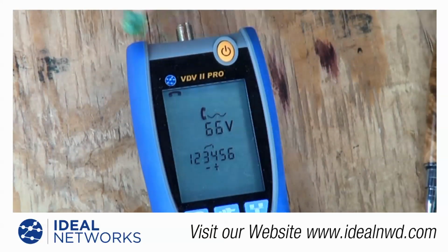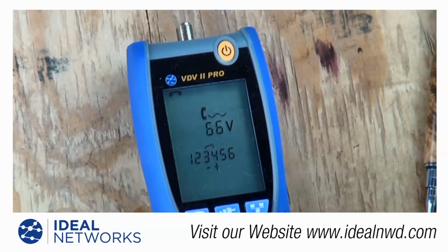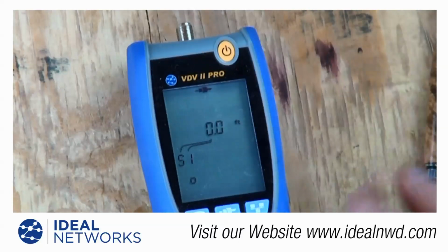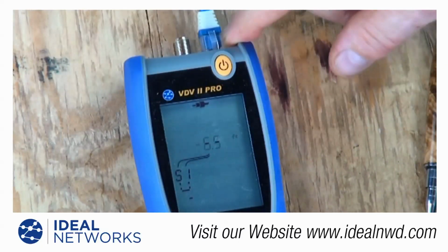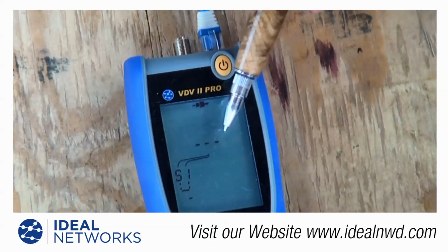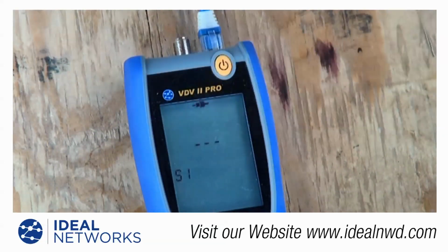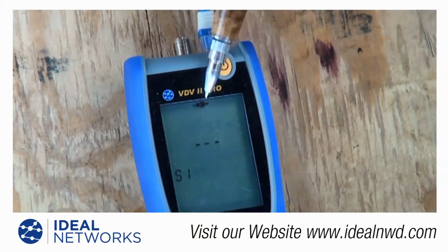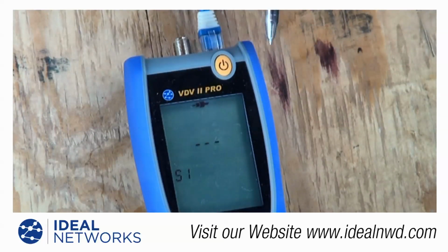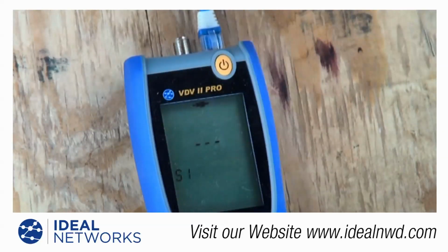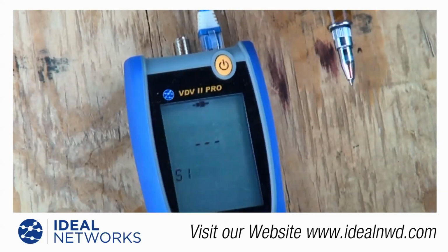The same thing happens in coax. Say if I'm in coax mode and I plug that computer back into the top of the tester - it's interesting, it's giving me the length of the patch cord, telling me it's shorted because the Ethernet switch on the other end has actually shorted it. Since I have it in coax and something plugged into the data port, the shared bus is looking at pins 4 and 5 related to what's on the plug. So it doesn't see the voltage because the voltage is being applied to 1, 2, 3, and 6. It's actually doing the testing for me and letting me change the mode.